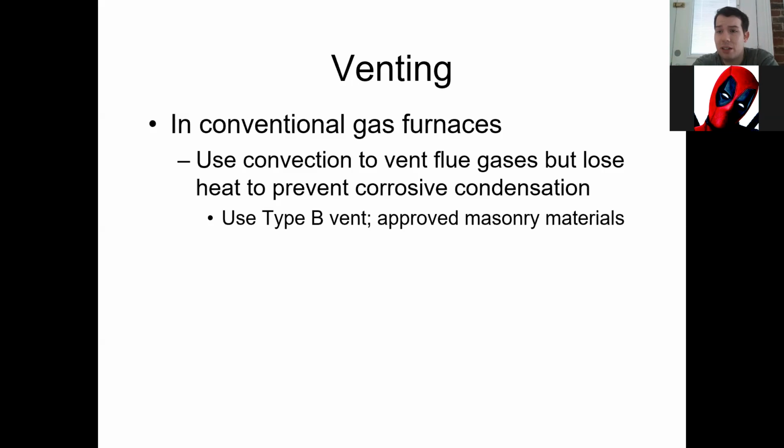You can also use a sealant as well to make extra sure that everything's good. There's an HVAC silicone you can buy that you use like a caulk gun, and you just bead it around the bottom of it and fill in the gap, and it works really well. So that's another way to make sure that your flue gases are 100% exiting the structure. So there's a lot of different things that we can do to make sure that that's happening. But the biggest thing we have to worry about as far as the metal vent piping is condensation.